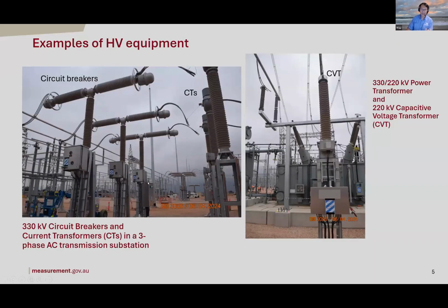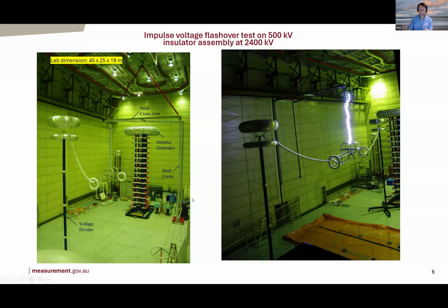Of course, we can do the testing in the manufacturing plants of this equipment when it is quality controlled before shipping out, or in the design stage, or in the substation just before commissioning. But another very common place we do this testing is called a high voltage laboratory. I'm sure many of you have seen this type of laboratory. This particular one is, say, 45 meters long, 25 meters wide, 19 meters high. It's a medium-sized high voltage lab. There are much bigger ones. In this example, you can see transmission line insulators with a simulated part of a tower being tested for withstand of lightning strikes. Under rainy conditions, you can see the pool here collecting water. So that's a very brief picture of high voltage testing to start with.